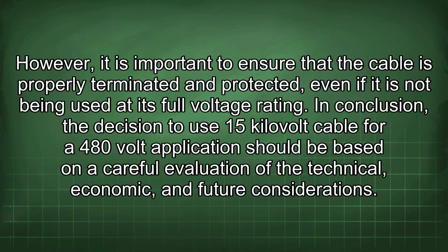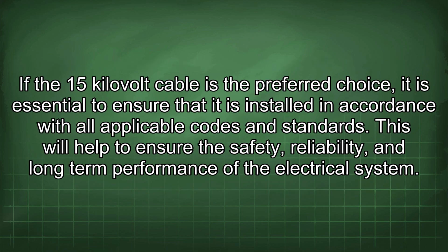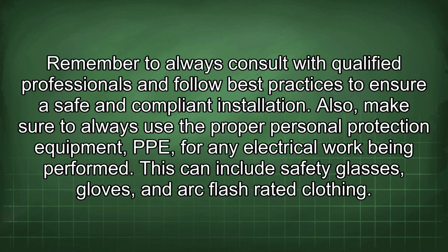In conclusion, the decision to use 15 kV cable for a 480 volt application should be based on a careful evaluation of the technical, economic, and future considerations. If the 15 kV cable is the preferred choice, it is essential to ensure that it is installed in accordance with all applicable codes and standards. This will help to ensure the safety, reliability, and long-term performance of the electrical system. Remember to always consult with qualified professionals and follow best practices to ensure a safe and compliant installation.